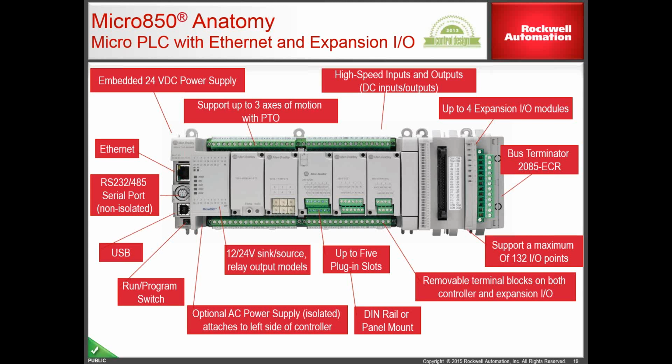So you can have 5 plug-in slots in this, and then it can go up to 4 expansion I/O modules, right? And it supports up to 132 I/O points. If you would like to extend this as a remote I/O configuration, that functionality is also there. There is a DeviceNet on which you can extend your number of I/Os.